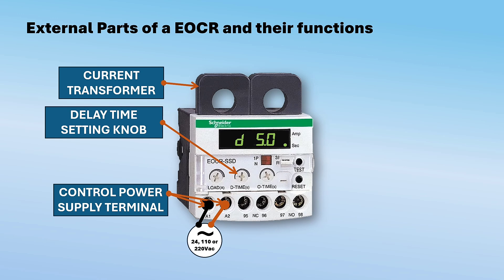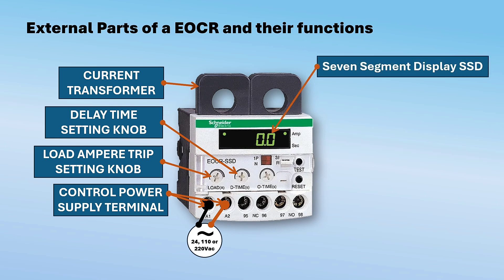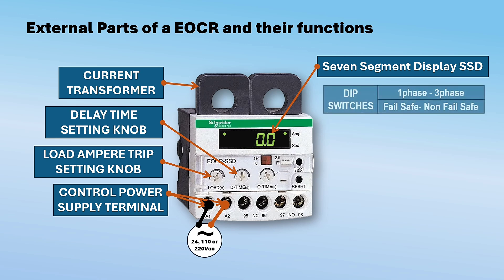The delay time allows current to return to a normal operating level before the EOCR trips. Ampere trip or load trip setting is used to set the ampere trip value of the motor as per the nameplate FLA. LED display — the display provides trip indication and ammeter functions; the cause of the trip is displayed and stays until reset is done to ensure easy troubleshooting. Dip switch — for single-phase and three-phase motor selection, and for fail-safe and non-fail-safe mode, which selects the tripping relay output.